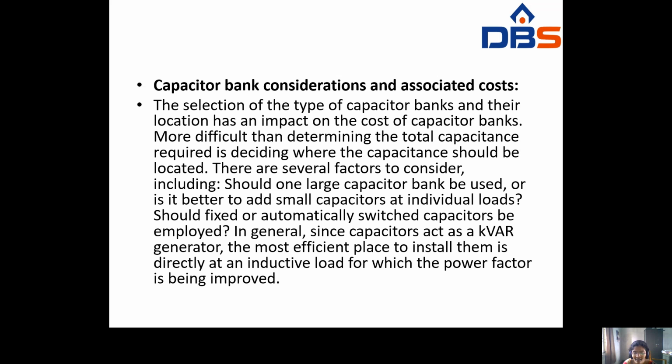In general, since capacitors act as a kVAR generator, the most efficient place to install them is directly at an inductive load for which the power factor is being improved.